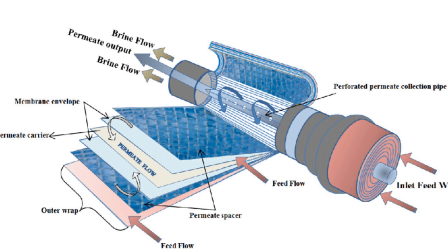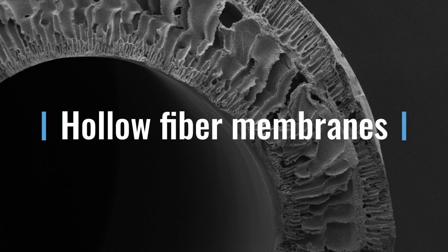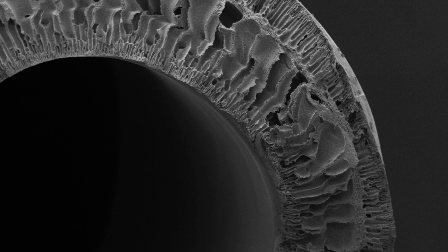It's important to note that reverse osmosis is not limited to the spiral wound configuration shown here. Hollow fiber membranes represent another promising alternative to the traditional spiral wound configuration. The conventional flat sheet or spiral wound RO membranes are usually able to withstand a maximum pressure of about 80 bar. By contrast, the hollow fiber membrane is self-supported and has a higher surface to volume ratio than the flat sheet membrane. The image shown here represents a hollow fiber membrane, which is easier to scale up and simpler in module fabrication than a flat sheet one.